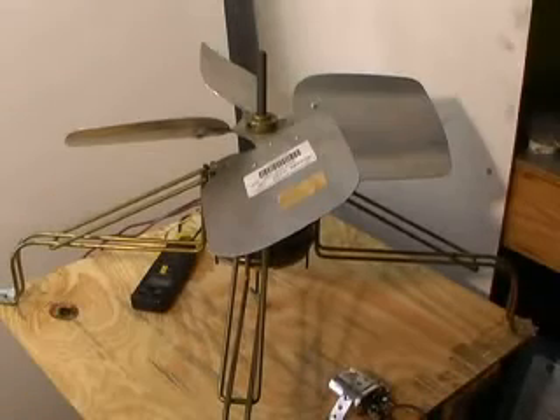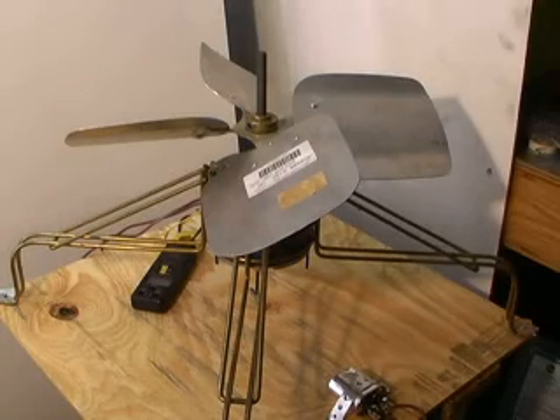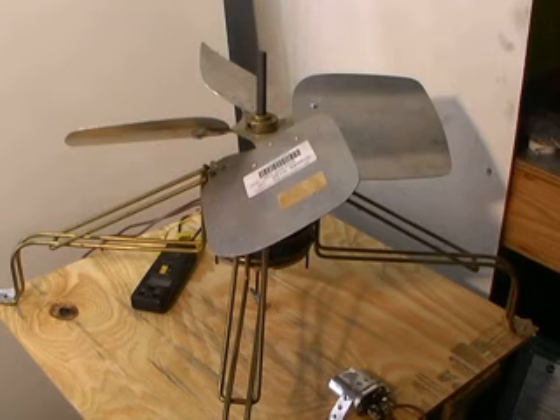Now we'll look at just troubleshooting fan motors, blower motors, condenser fan motors, either way. What I'm going to do first of all is start up this new motor that I've got set up, and see how they're supposed to start and how they're supposed to sound. Then we'll play with the capacitor and see what kind of symptoms you get when the capacitors go bad. When they start up, it'll just be a quiet start, fairly quick start, no roars, no rumbles, no grunts, no groans.